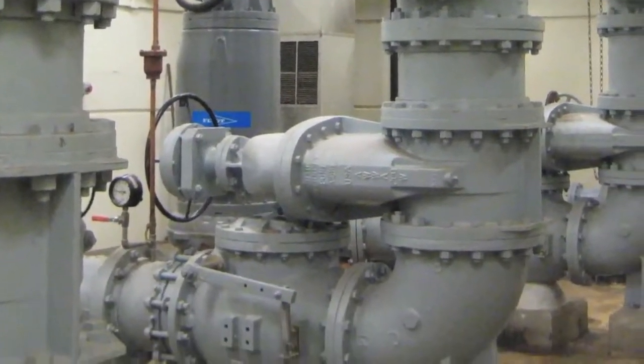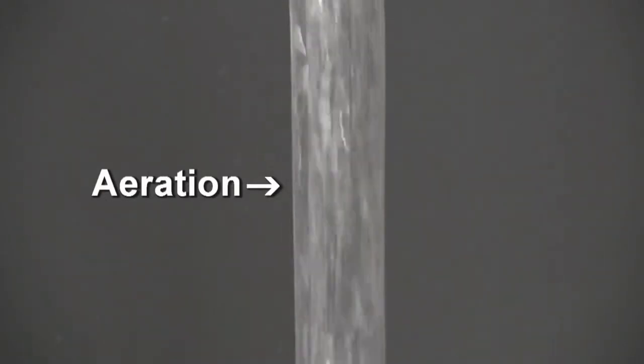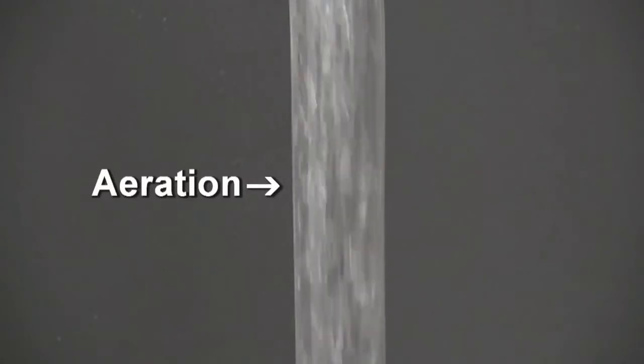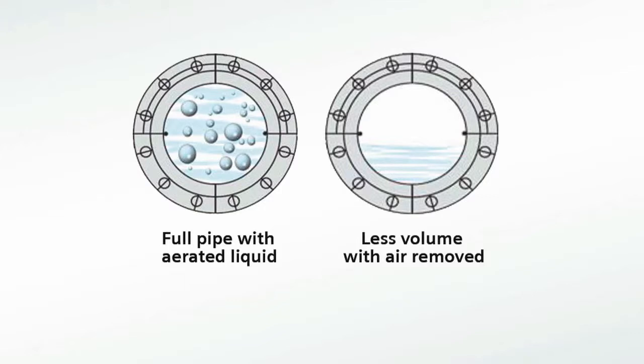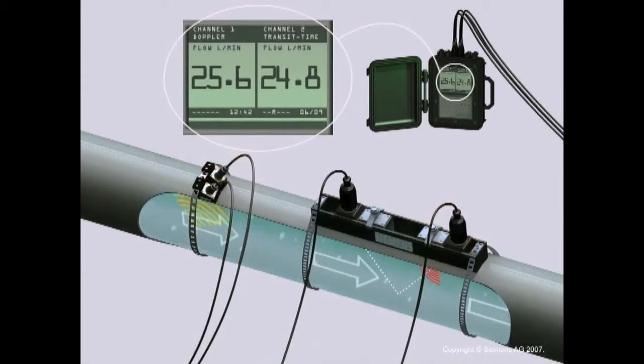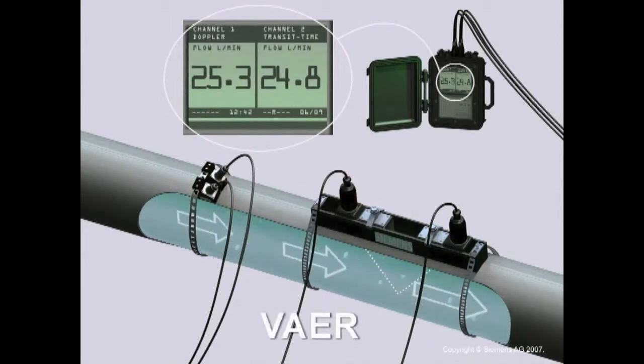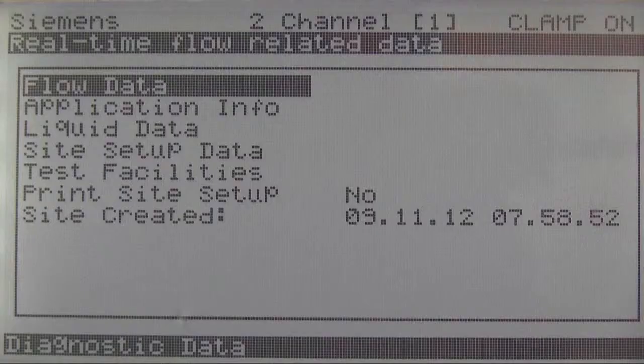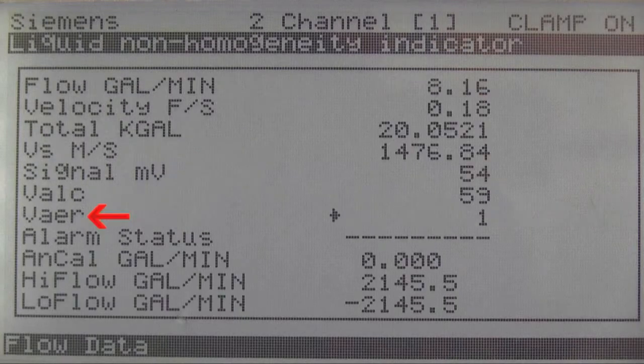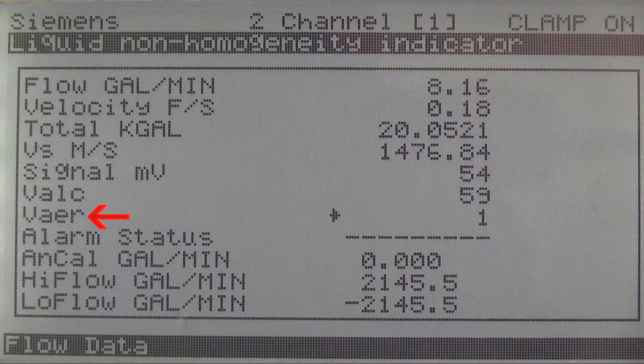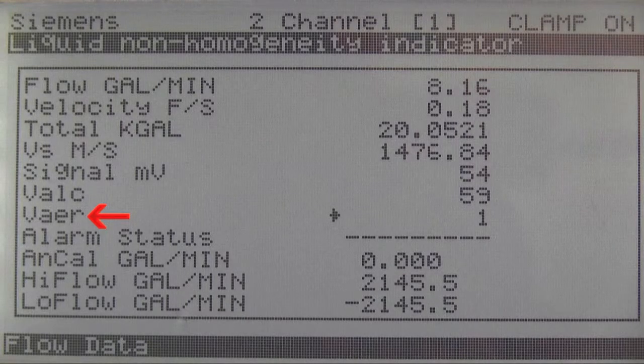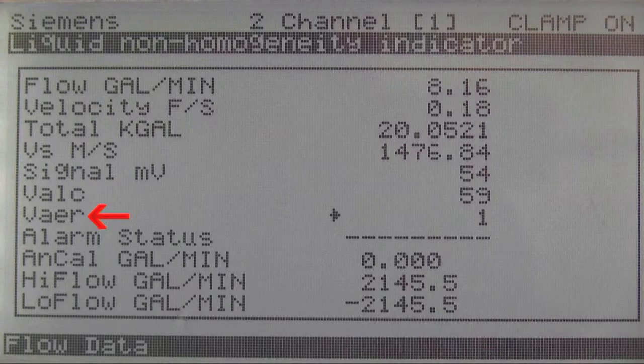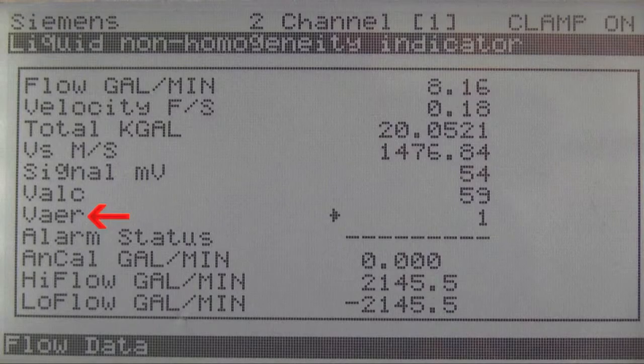Sometimes liquids can be aerated due to cavitating pumps or valves, or air trapped in the system, without the user being aware of its presence. Aeration will impact the accuracy of any flow meter, clamp-on or intrusive, since air occupies space in the pipe. Siemens clamp-on flow meters are excellent detectors of aeration, and report it with the diagnostic parameter VAER. It can be found in the flow data menu we looked at earlier. VAER is a value between 0 and 100. Lower is better. Values less than 10 indicate insignificant amounts of aeration. All higher levels will indicate the magnitude of entrained air.